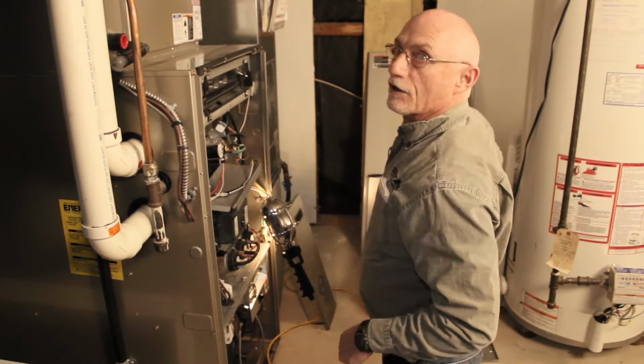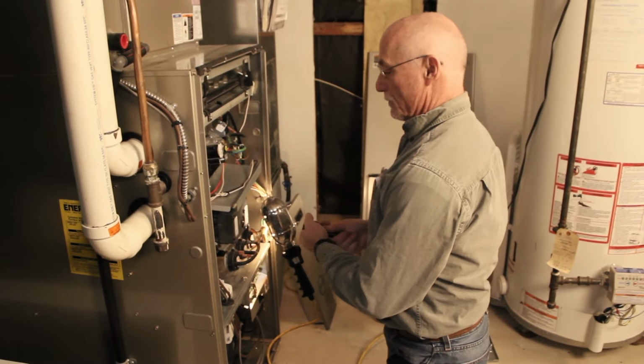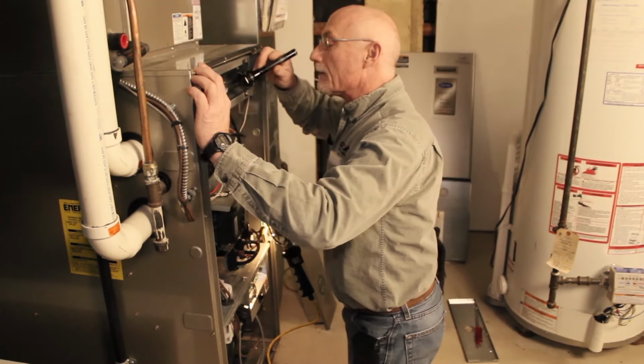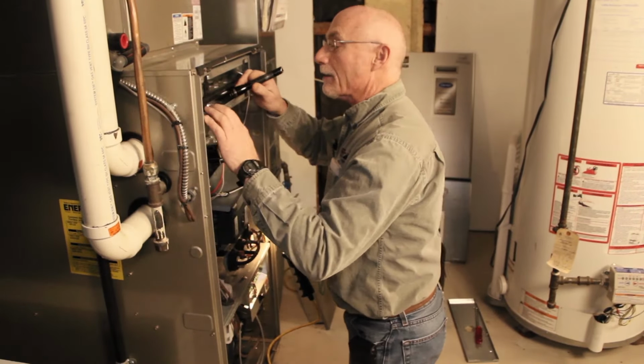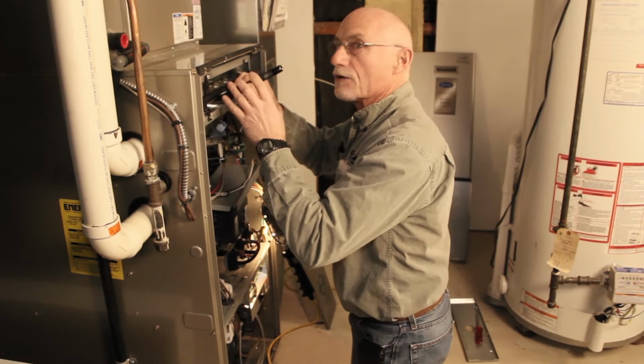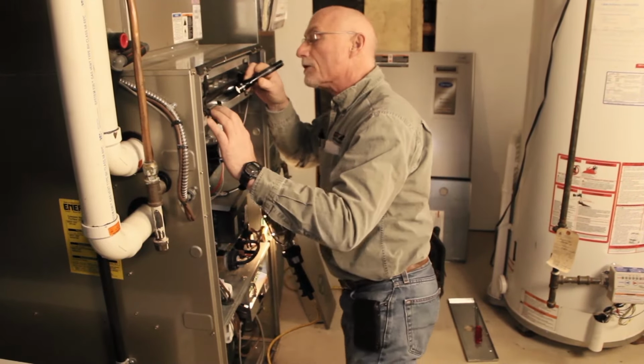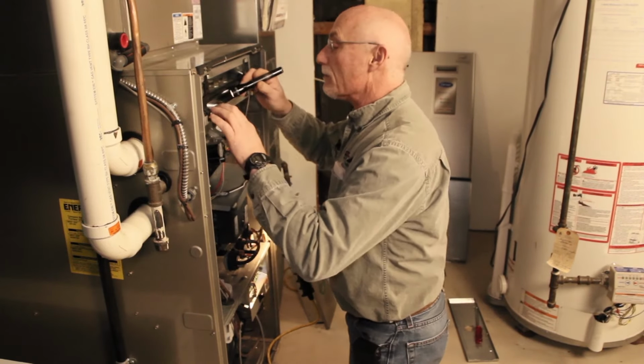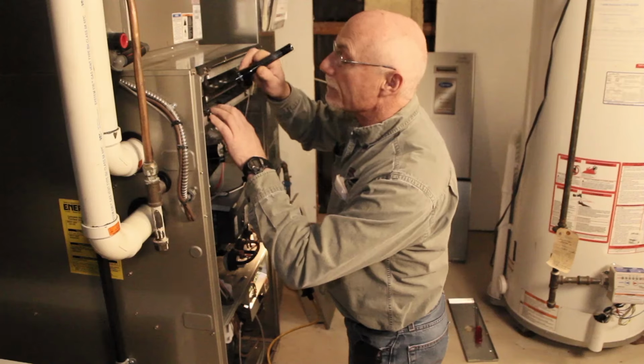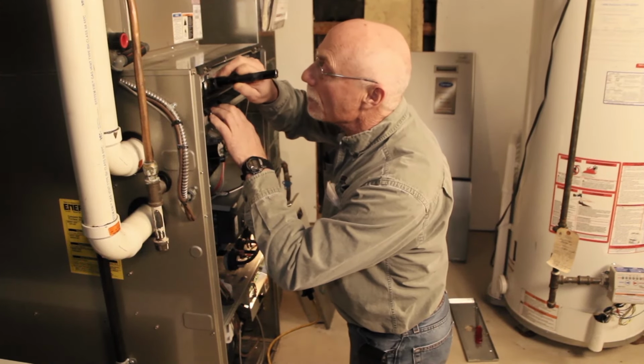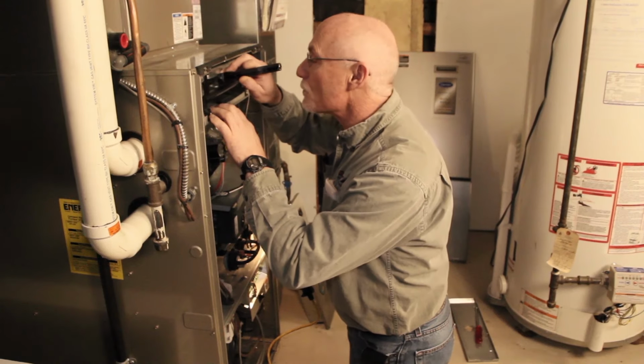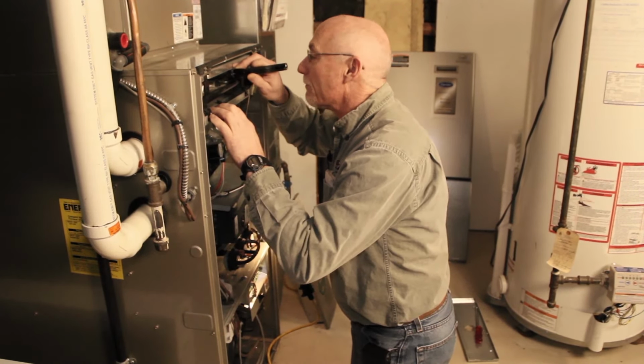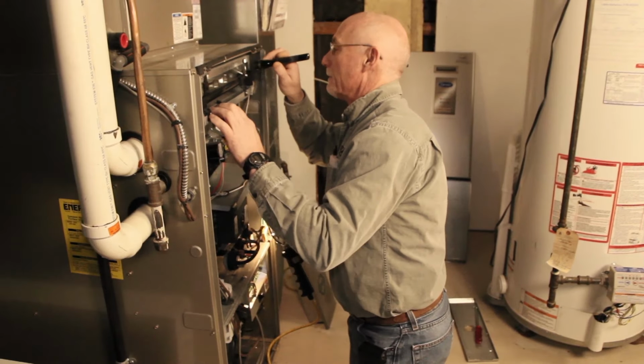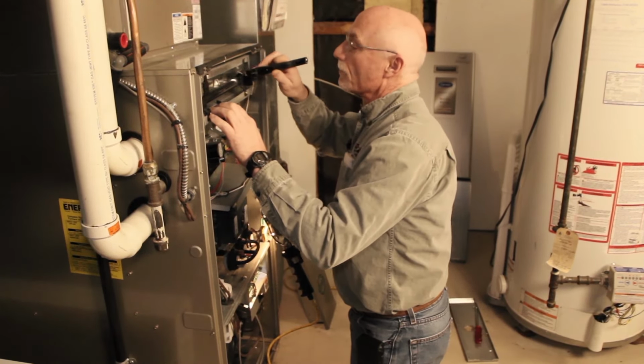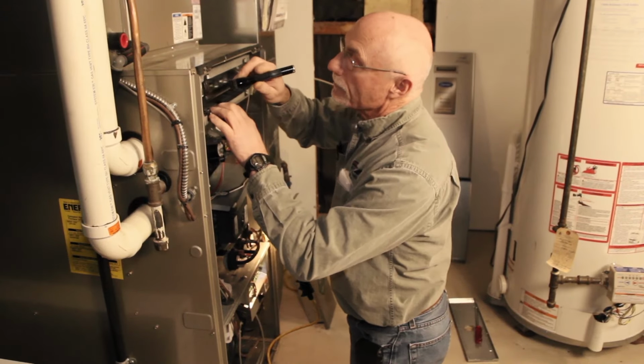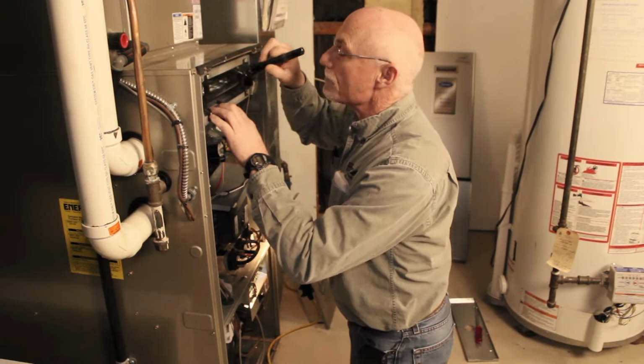So with this panel off, it actually now allows me to take a good peek inside and see what's going on. We've got a pipe that's from the outside and that can get plugged up with leaves. Sometimes it can be brought into the area here where the combustion air is. We want to make sure that nothing's been sucked up from the fall when all the leaves were flying around. And visually look into the heat exchanger, make sure that there's no signs of any rust or anything of that nature or deterioration of it. And again down to the burners, make sure we're all good. And that part of it all looks fine.